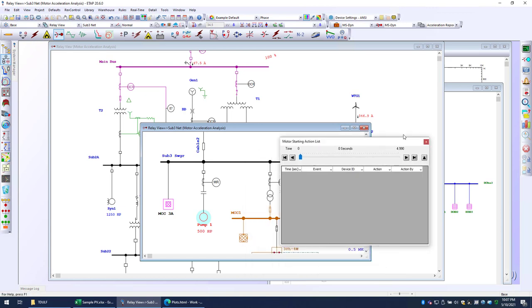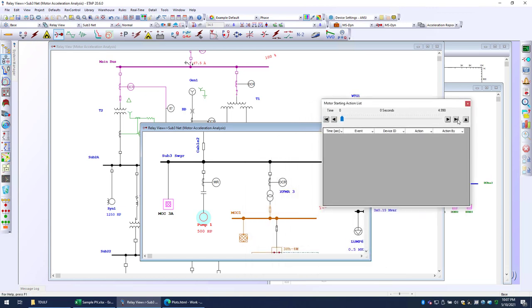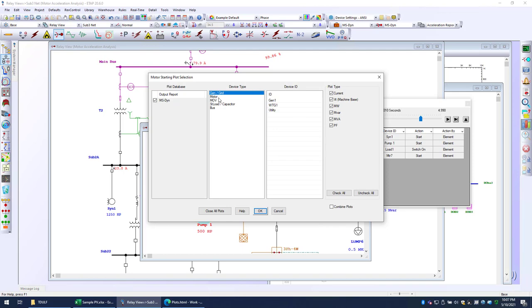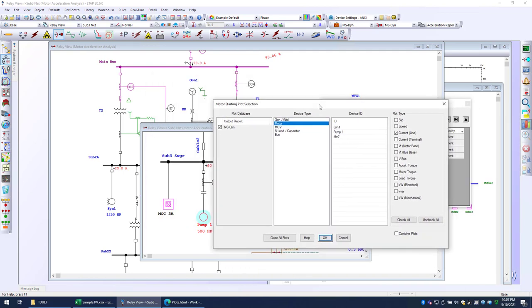And here is the action view, so I could step through the different events. So here is where we start the two motors at 100 milliseconds. At 800 milliseconds, there's a load that gets switched on, and at 4 seconds, the next one.